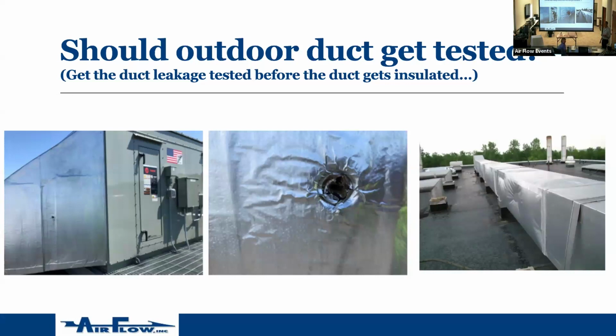looks like a field, good news, bad news. The good news is the contractor did a field pressure test. The bad news, he probably should have done it before the duct was insulated. So he's got peel and seal, and then he had to punch a hole in it to do the pressure tests. Get that pressure test done before there's upside and downside to that too. We'll talk about that the next hour when we're talking about more outdoor duct.